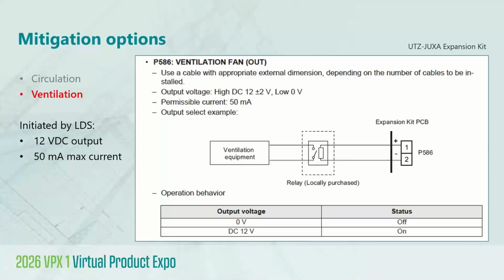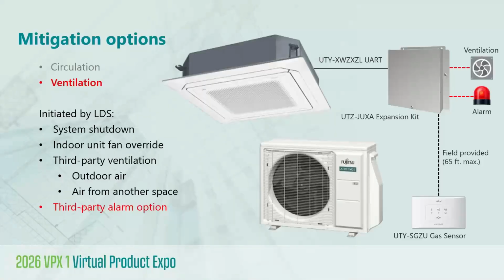And that's ideal because it meets the output requirements and really is readily available at distributor locations and is inexpensive. Now, what I like, a great convenience, is that when you connect to the expansion kit inputs or outputs, we now use pushpin type connectors. So that means no additional cable accessories are required. So the expansion kit also provides an additional 12-volt DC output that can be used to activate a third-party alarm, like you see there just below the ventilation fan. So it's important to note that the alarm can be used in conjunction with the ventilation fan or independently for notification purposes only. Really, the specific use of the ventilation and alarm outputs will depend upon the details of the mitigation requirements for the project.